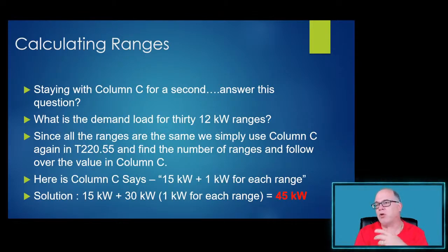So when I'm doing the load calculation under the standard method, and I have 30 ranges in my overall load calculation for that multifamily building, then the contribution for that range load is what? 45 kW. And I simply add that into my equation, okay? Now, we're going to cover all this in my multifamily dwelling video, where I plug in some of these examples. But again, to be honest with you, when it comes to ranges, it's really just that simple, right? All right, let's do a little more.